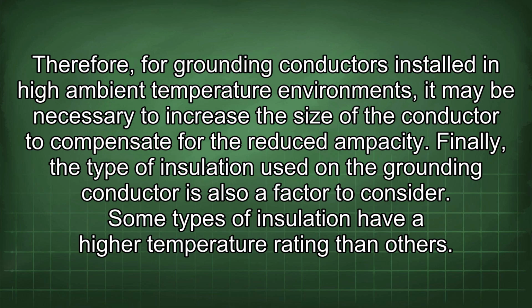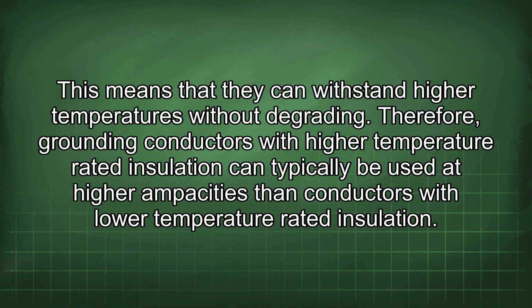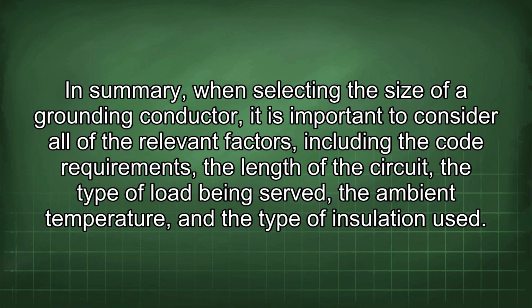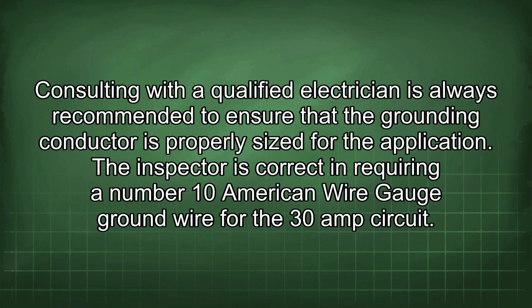Finally, the type of insulation used on the grounding conductor is also a factor to consider. Some types of insulation have a higher temperature rating than others. This means that they can withstand higher temperatures without degrading. Therefore, grounding conductors with higher temperature rated insulation can typically be used at higher ampacities than conductors with low temperature rated insulation. In summary, when selecting the size of a grounding conductor, it is important to consider all of the relevant factors, including the code requirements, the length of the circuit, the type of load being served, the ambient temperature, and the type of insulation used. Consulting with a qualified electrician is always recommended to ensure that the grounding conductor is properly sized for the application.